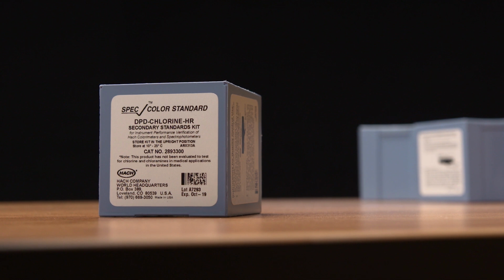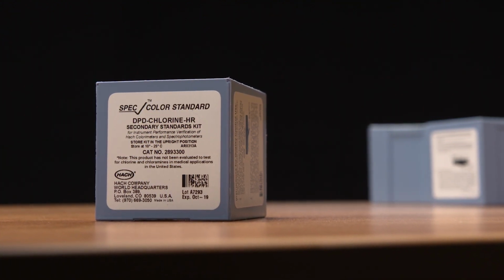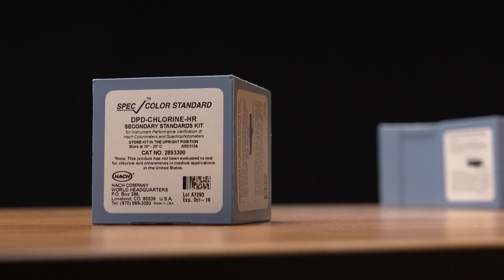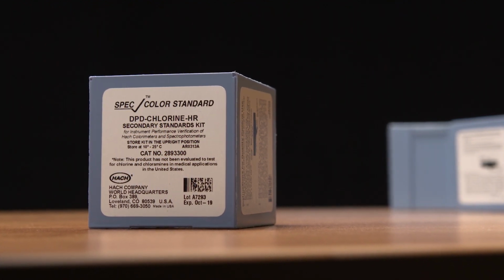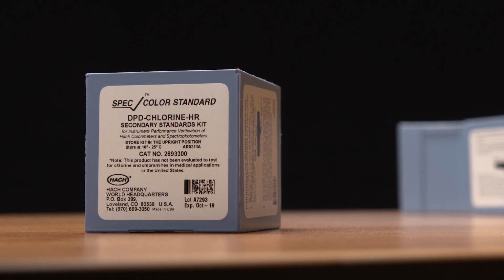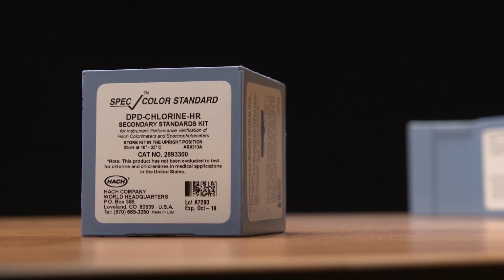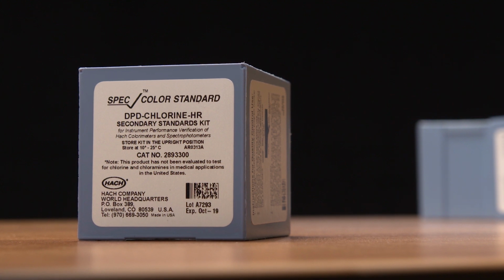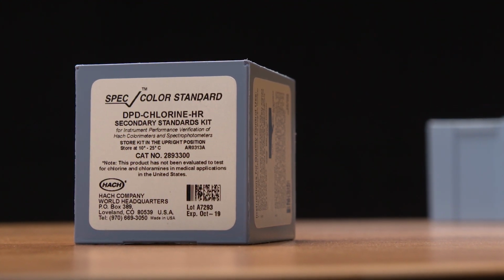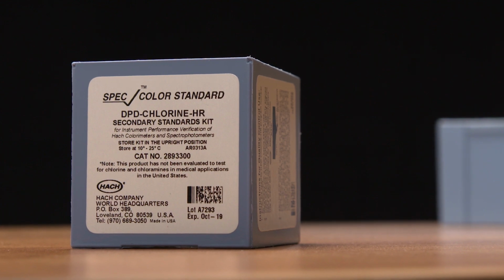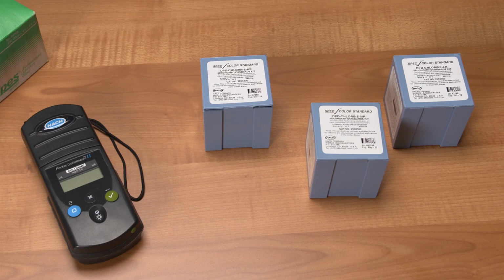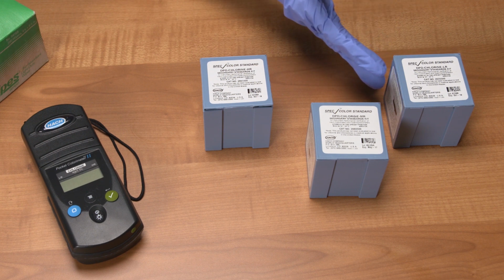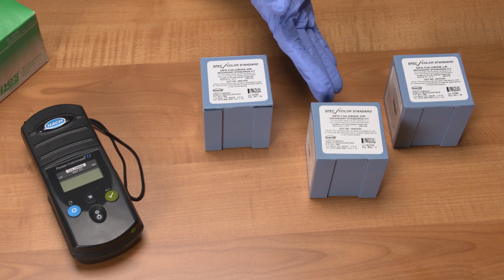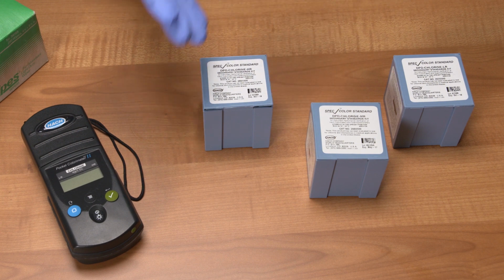Note that use of the secondary gel standards should not fully replace the use of primary dilution standards during a routine quarterly calibration verification. Secondary standards can be purchased from your instrument manufacturer and should span the entire range of concentrations that your instrument will be expected to measure. Note that secondary standards are not available for all colorimeter models. This equipment manufacturer provides secondary standards in 3 ranges: low range, from 0 to 2 milligrams per liter, mid-range, from 0 to 4 milligrams per liter, and high range, from 2 to 8 milligrams per liter.